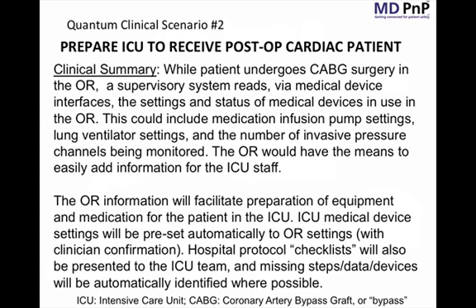So the system can read the ventilator settings from the anesthesia machine, and read the infusion pump settings from all the infusion pumps. That would include reading the name of the medication, the infusion rate, things such as that. Also, any other medical devices that are being used with the patient, their status would be read, and other relevant data would be obtained from the OR team. If it can't be obtained automatically, directly from a medical device or directly from the EHR, then there will also be a means for the staff to manually enter requests or specific information. One would assume that allergy information will be able to be pulled from the EHR, but there may be difficulty in assessing other things directly, and that will require information from the staff.